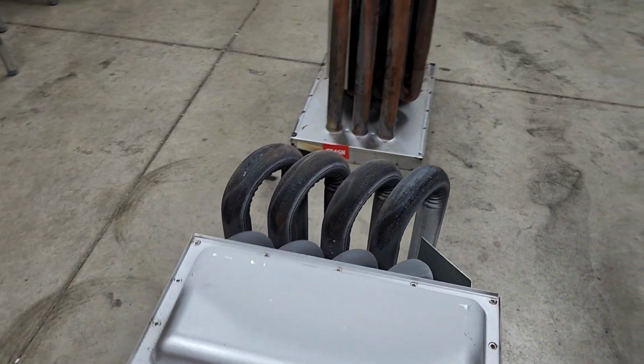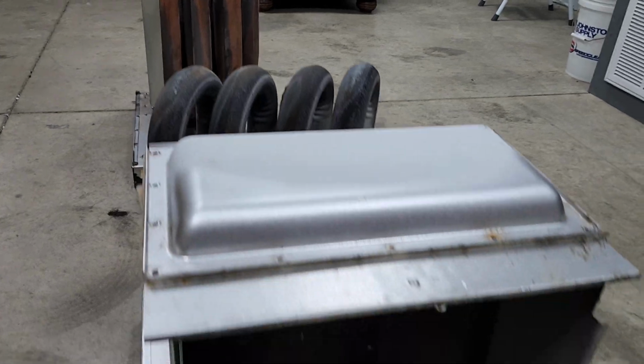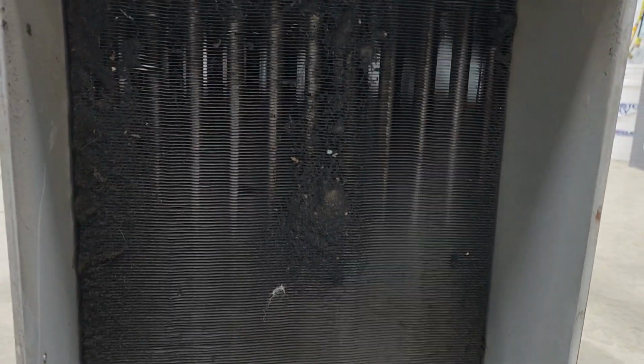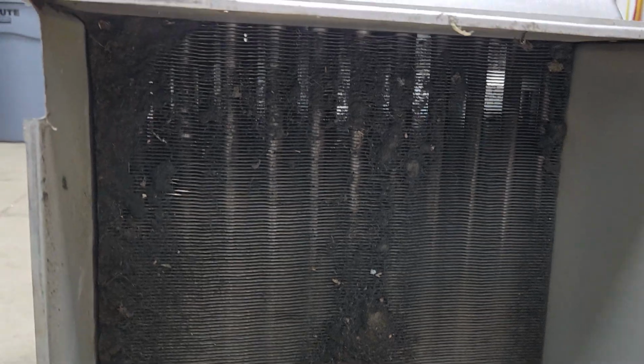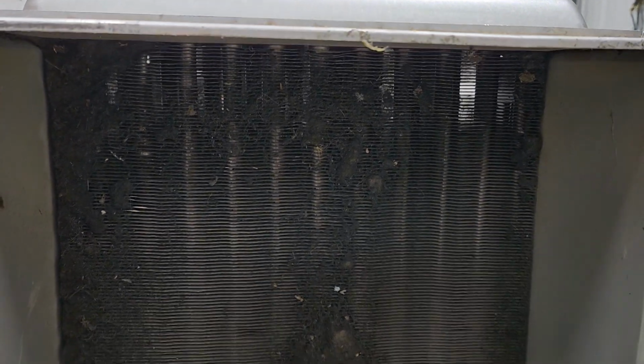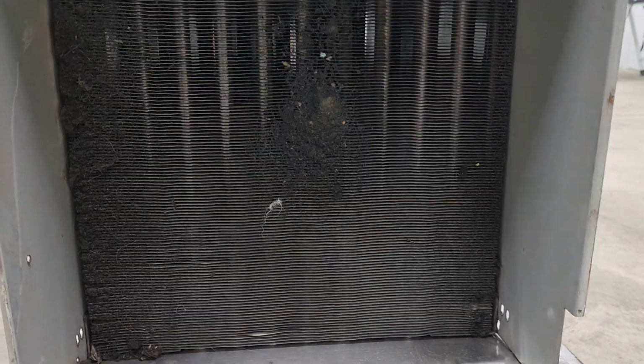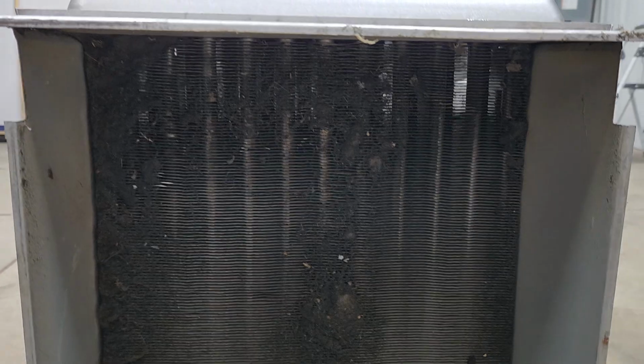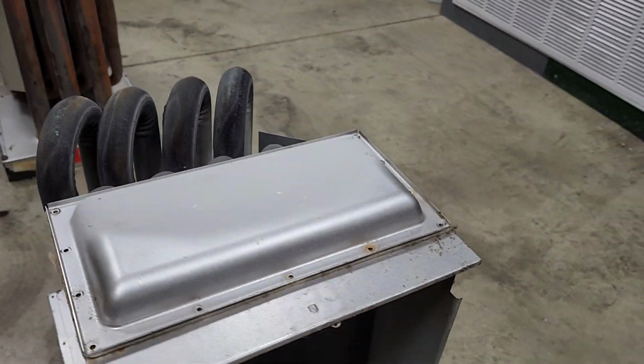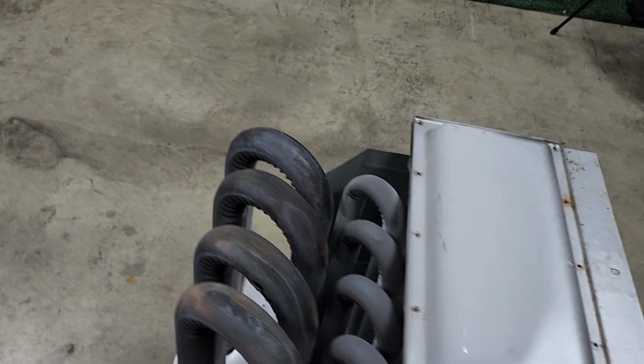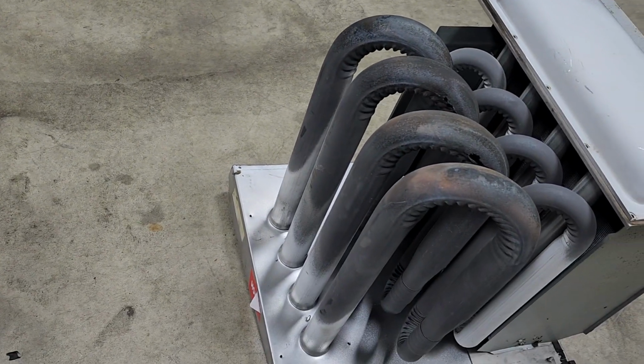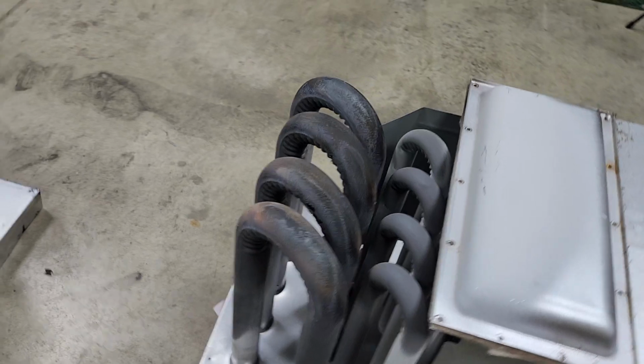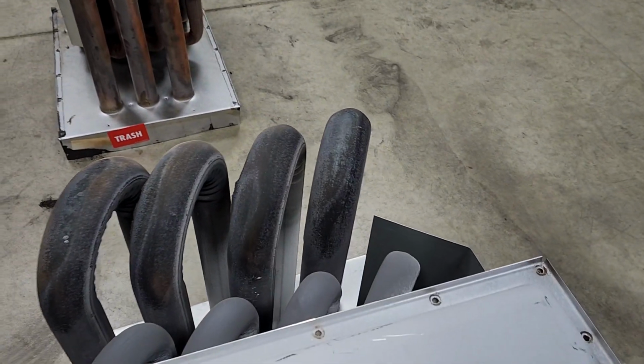Another preventative method is basically on the homeowner's end of things. As you can see here, the secondary heat exchanger, which is usually above the blower motor, is caked full of crud. This is something that the homeowner could have done to help prevent this heat exchanger failure, simply by replacing their filters on time, or even just putting a filter in the return air duct system to catch some of that stuff, so that we can have clean air going across this unit. So this unit was probably condemned and returned because of pressure switch faults, with the holes in it.